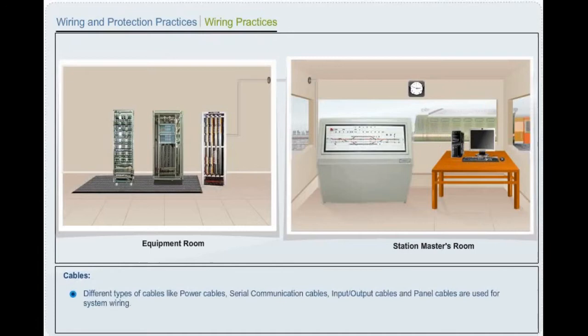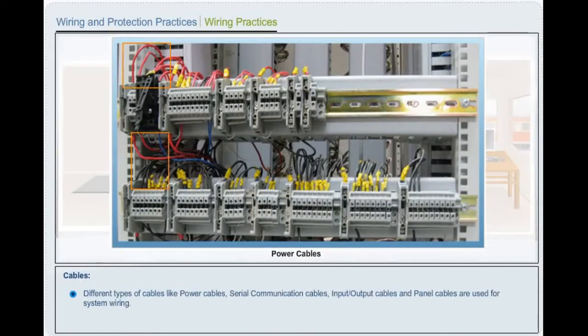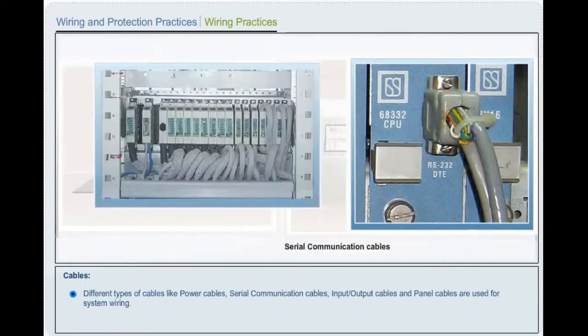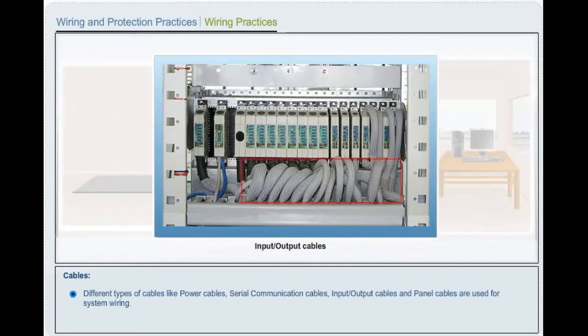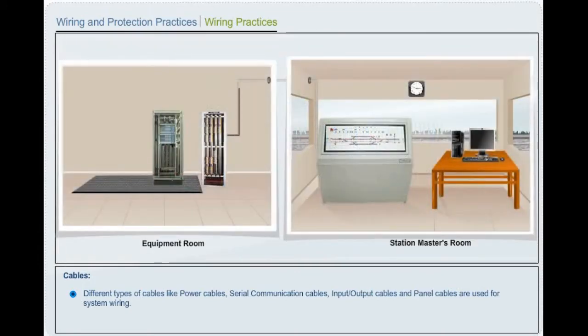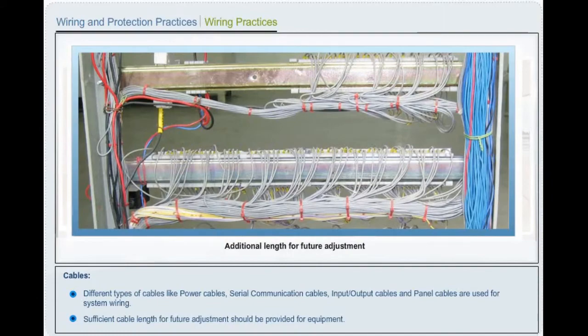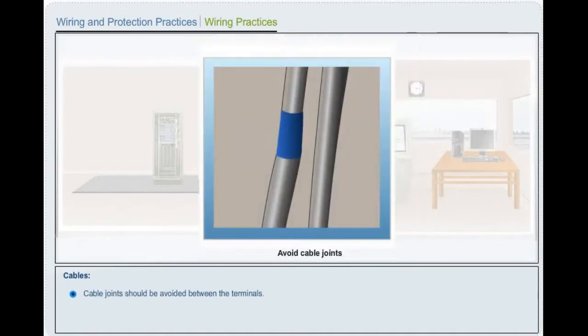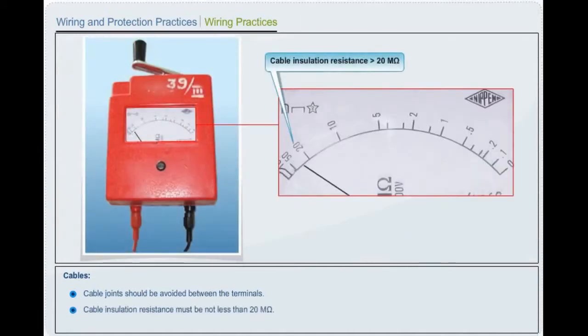Wiring and protection practices. Wiring practices. Cables. Different types of cables like power cables, serial communication cables, input cables, output cables, and panel cables are used for system wiring. Sufficient cable length for future adjustment should be provided for the equipment. Cable joints should be avoided between the terminals. Cable insulation resistance must not be less than 20 megaohms.